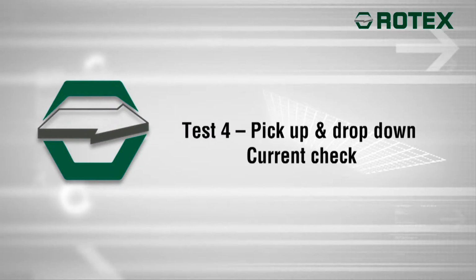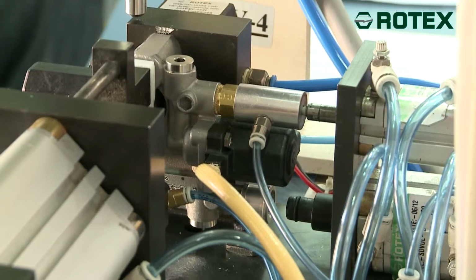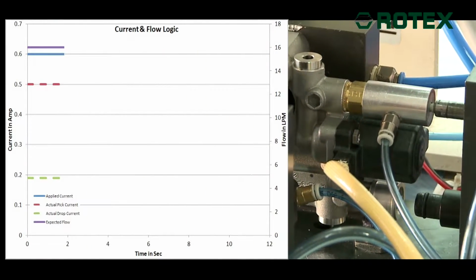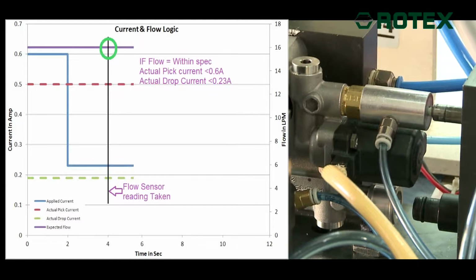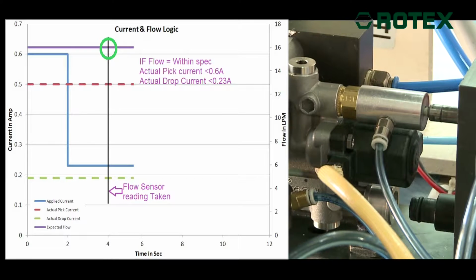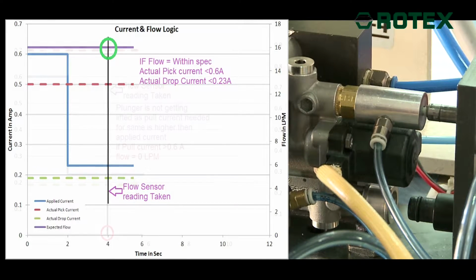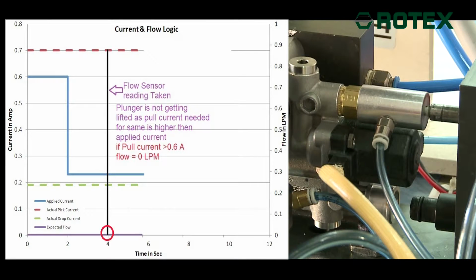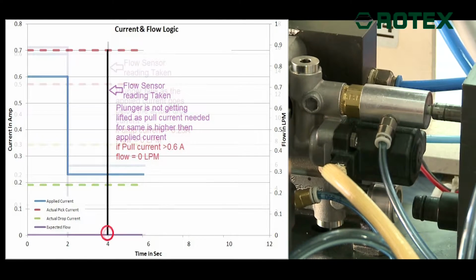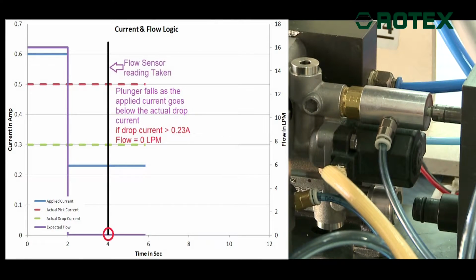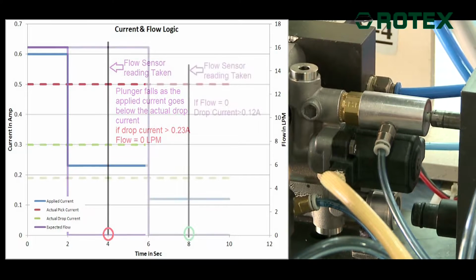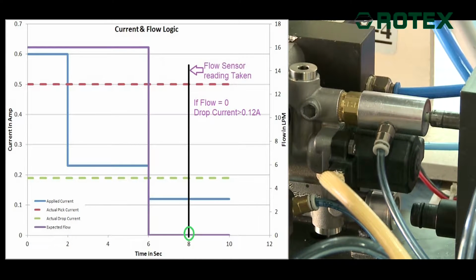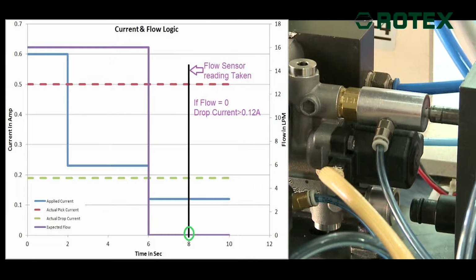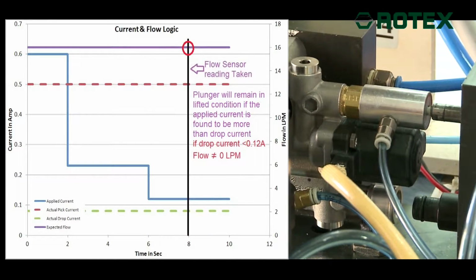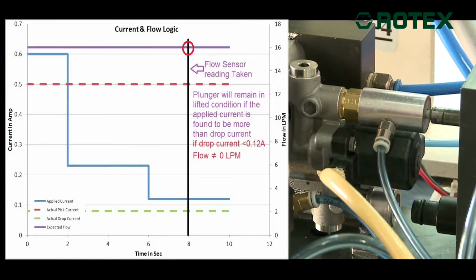Test 4. Pick up and drop down current check. During the flow test, the solenoid is energized with 0.6 amperes for 2 seconds and then it is dropped to 0.23 amperes for 4 seconds. Thus, the reading of the flow is recorded. In case of pickup current higher than 0.6 amperes or drop-down current higher than 0.23 amperes, the flow will be shown as 0 LPM. After this, the current is dropped to 0.12 amperes and the solenoid is expected to close. If the solenoid does not close, it will show airflow and this will be sensed by the flow sensor, indicating an error code through PLC.